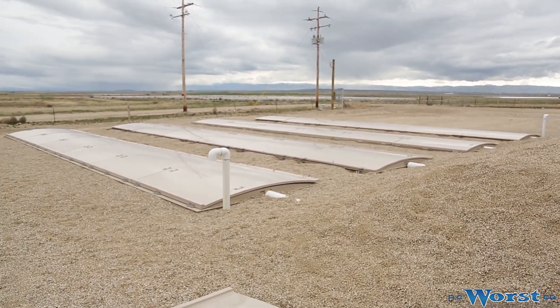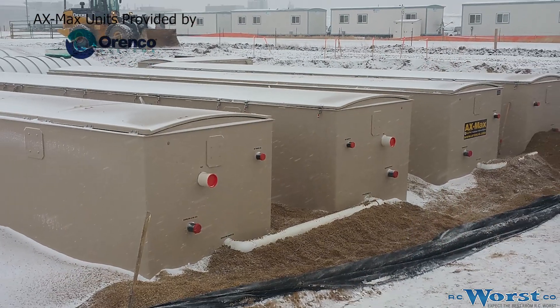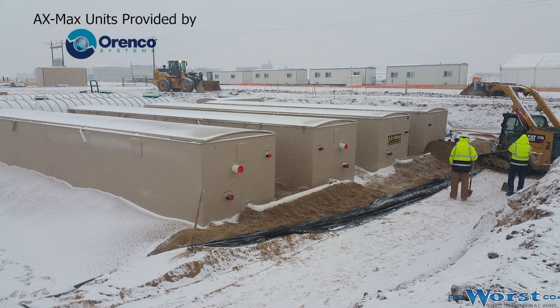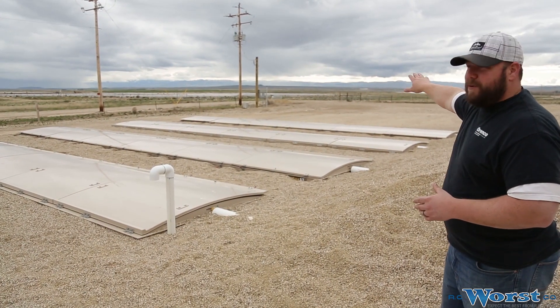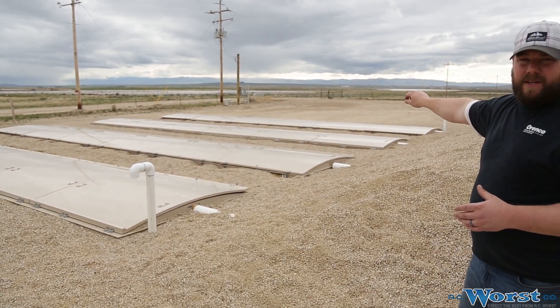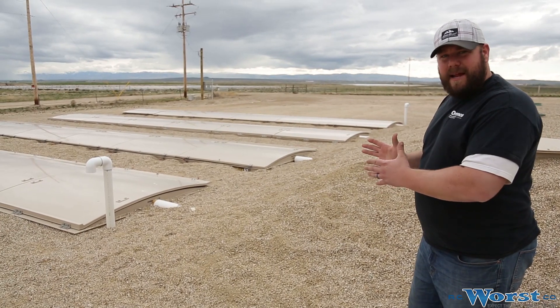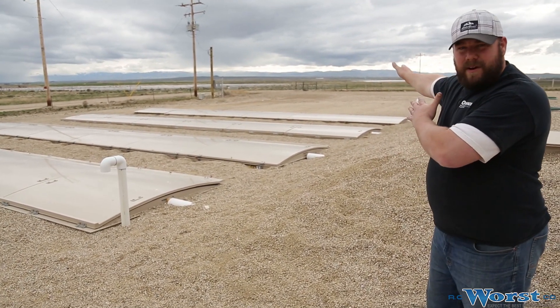What you see out here are four 42-foot AX Max treatment units. Each unit contains 300 square feet of textile for a total of 1,200 square feet of textile media. The first two units furthest away from me are what we call our recirc blend units. Our primary tank effluent, blended through this pre-anoxic process, flows over to that very first tank.